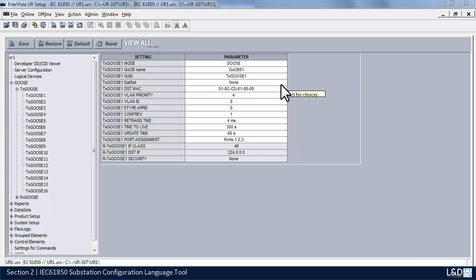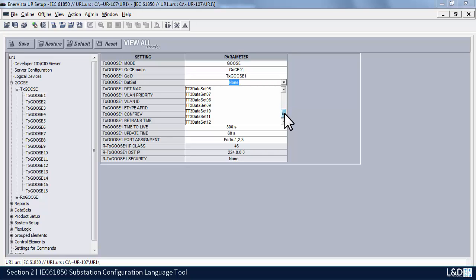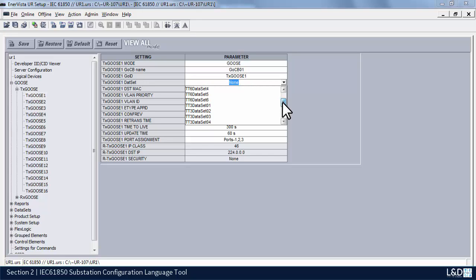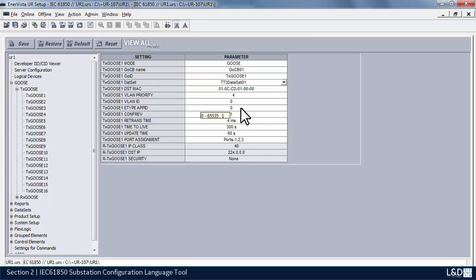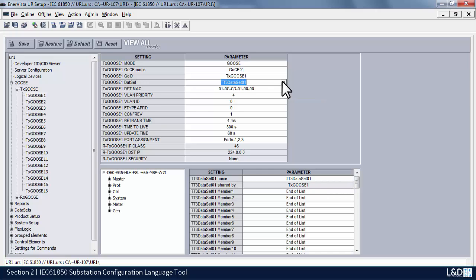The next field is the dataset. We have a choice of either TT6 datasets or TT3. There are 6 TT6 datasets and 12 TT3 datasets. The TT6 are known as our FAST datasets. When we populate a GOOSE message with the FAST dataset, it's considered a FAST GOOSE. If we populate it with TT3, it's considered a slow GOOSE — typically used for analog and non-mission-critical signals.